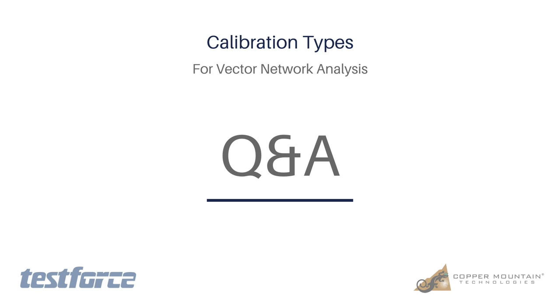Now, if we were only operating at a high frequency, say 6.4 to 6.5 gigahertz, we wouldn't see the arc even starting at the anticipated place at 180. It would start somewhere up and only be a small arc. That can be a little disconcerting, particularly if you've done a calibration, say from 6.4 to 6.5 gigahertz, and you attach the open, and now you see a tiny arc at 42 degrees. That doesn't look like an open at all, but that really is what it should be, because that's just the portion of the arc that we saw earlier.